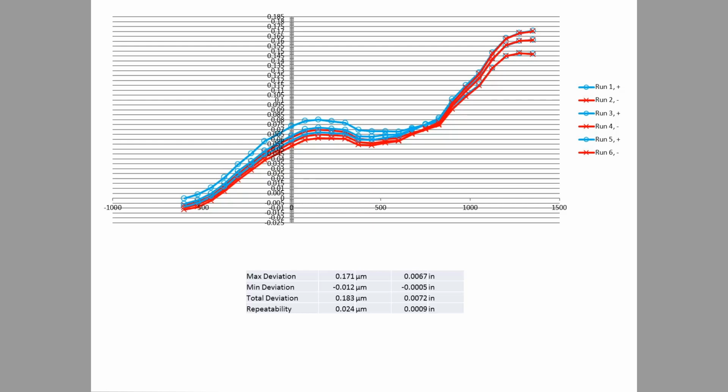So let's say we apply a comp value which is perfect for this middle point. We'll say that that's 160 micron. So I apply a comp value of 160 micron to that. If we get a test run which is exactly the same as our middle run again, it comps out beautifully. If I apply 160 micron of comp to my bottom line, then I get a negative value when I run this for verification. I've applied too much comp. And if I look at my top one, I've applied too little. This is the problem with repeatability.